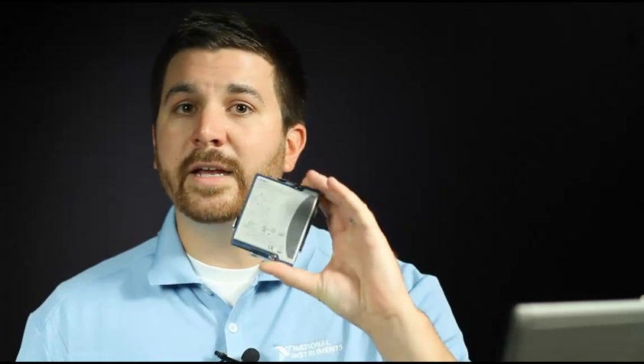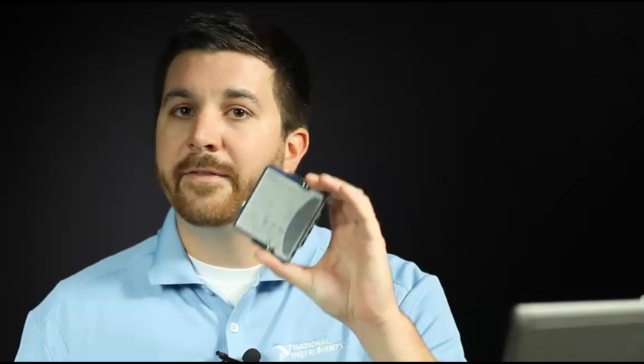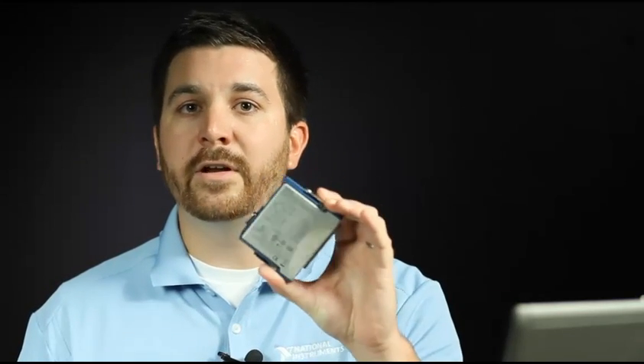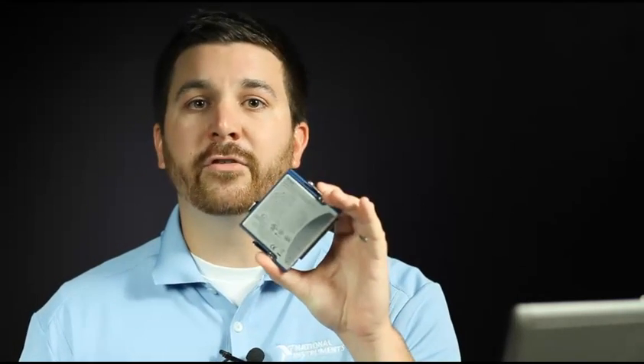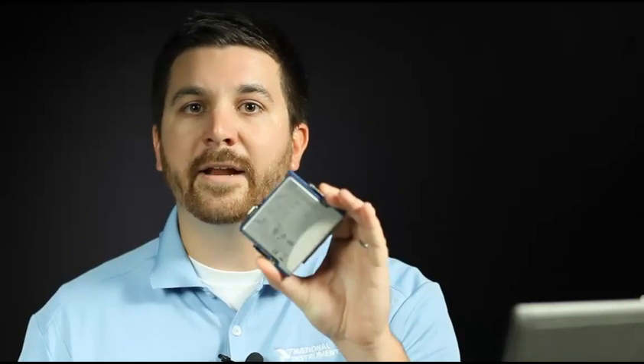So normally you need a couple things to measure a load cell. You need something to provide an excitation voltage. And also, since the load cell only outputs a signal in the millivolt range, you need some sort of signal conditioning to amplify the signal. And then lastly, you need a data acquisition device to measure the signal. So in this case, we're going to be using an NI C-series device that combines all those functions into a single module. It provides the excitation voltage, the signal conditioning, and the measurement.